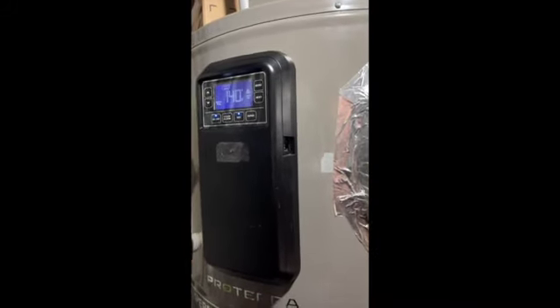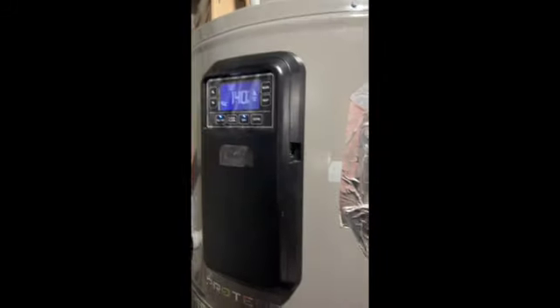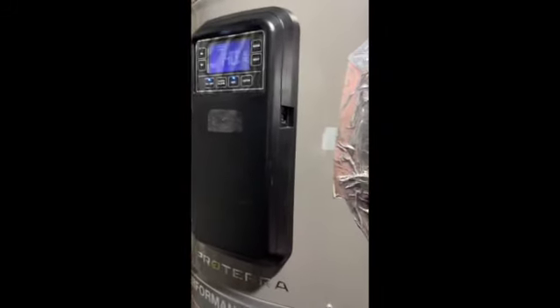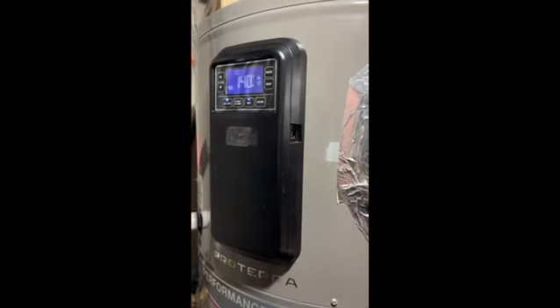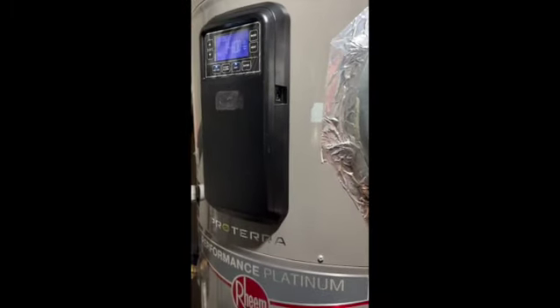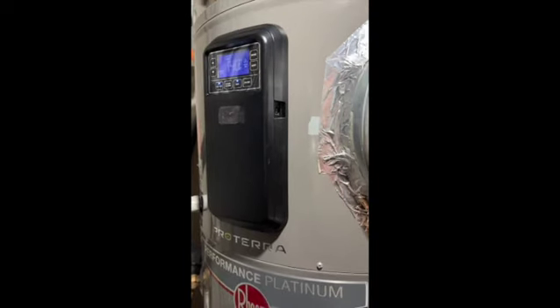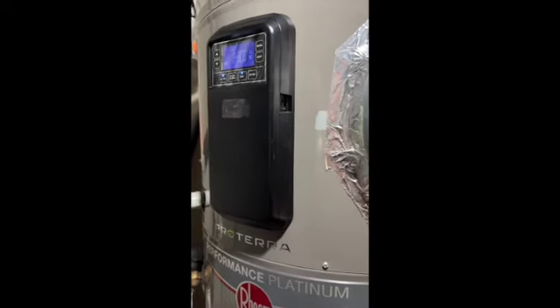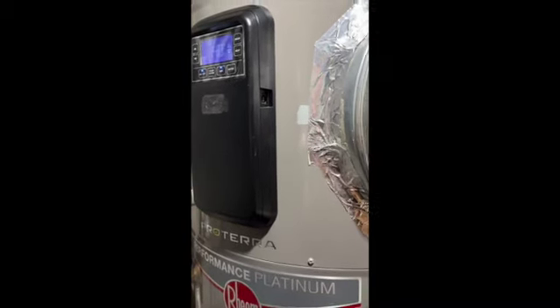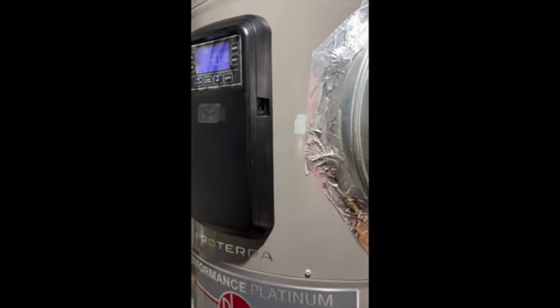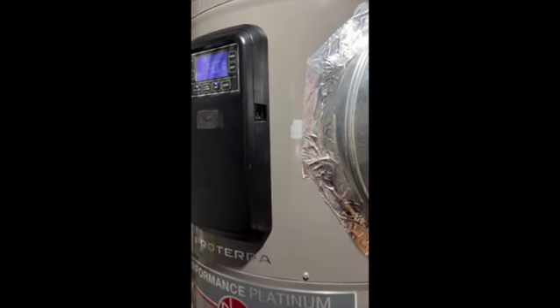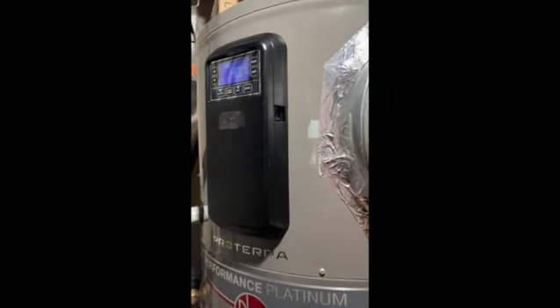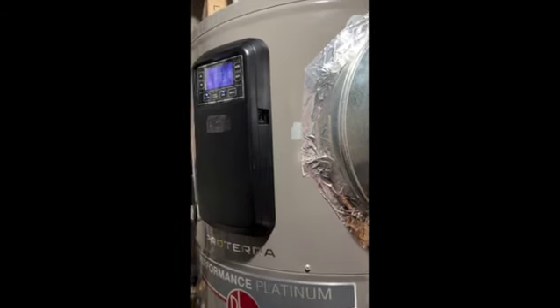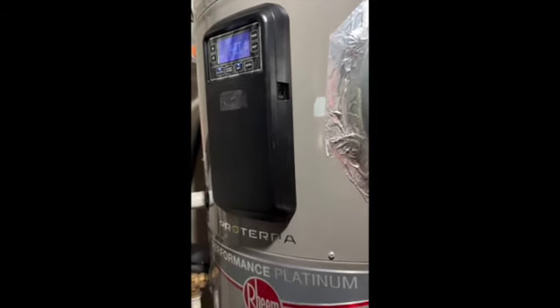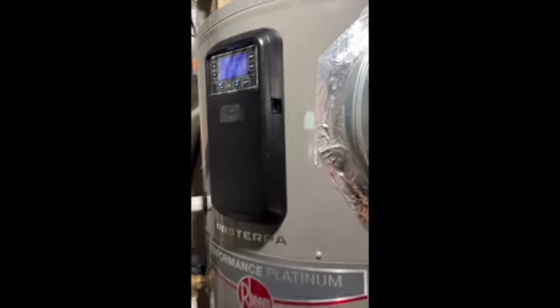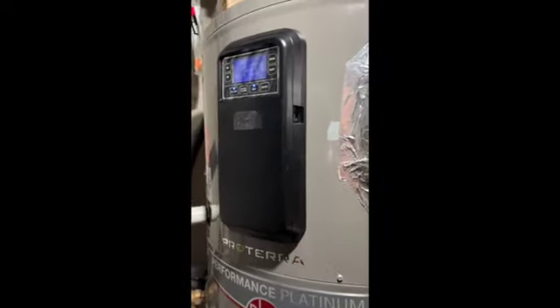What other questions? If you run it at 110 — that was a question — yeah, you'll run it a lot less because you're not trying to heat as far, and depending on your water intake temperature, like we're on a 300-foot deep well, we get quite a dynamic amount of cold water coming in, so it has a big range to heat up. That's why we run it to this point, because we want a lot of hot demand for the nights after sports and stuff. So if you run 110, which I did for a while, it did really good. At 120, it did really good. At 140 it does really good too, but you use more energy — you have to heat it more.